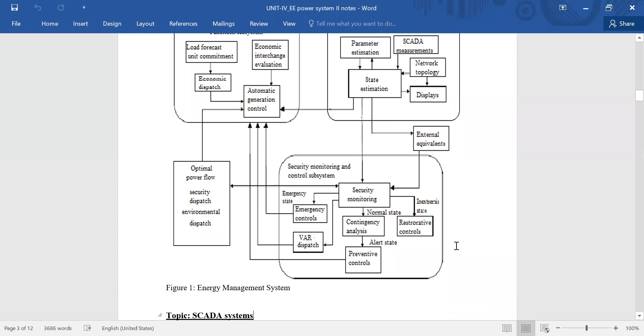When we are talking about SCADA, the SCADA system is the supervisory control system. It normally consists of a computer system and a number of RTUs, that is remote terminal units, which are located in power stations and substations. The communication between the RTU and the computer usually takes place via radio links or via power line carrier equipment. The computer serves the personnel in the control center by presenting information about the current status of the power system, and by passing on manually initiated control actions.